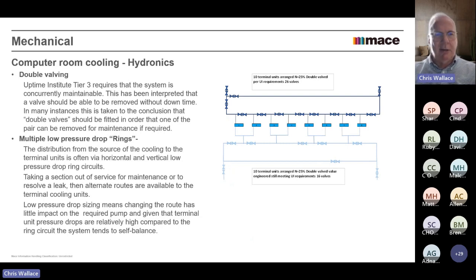And if you look at, as I did recently, a 750 mil diameter butterfly valve for a ring main on the roof of a building, the mean time between failures measured by some Norwegian oil experts is 21 years. So you think, well, do we really need to put two of those in?